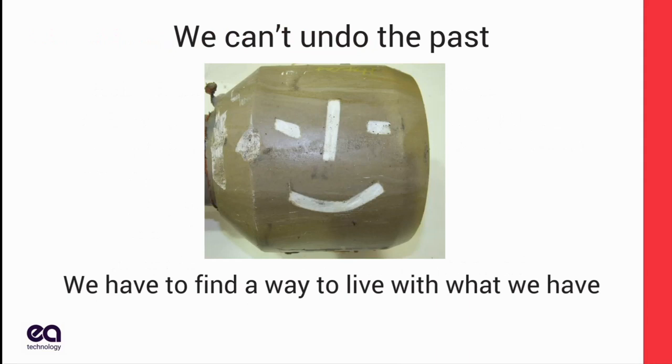Many workmanship issues can be improved through training, but you can't fix everything. Here's a picture from one of our failure investigations. The joiner did not know what to do with the white tape. So he found something to do with it, probably not the best use of that tape, and that joint failed, not surprisingly. But that's out there. We've got those things out there. So how do we live with all these mistakes that are living out there now? We have to find a way to live with that.